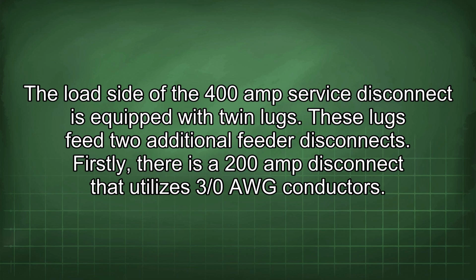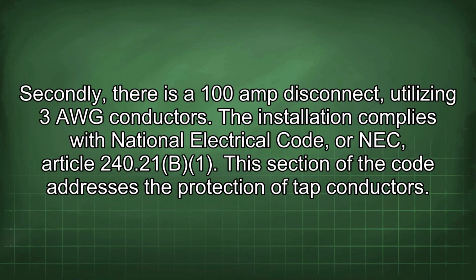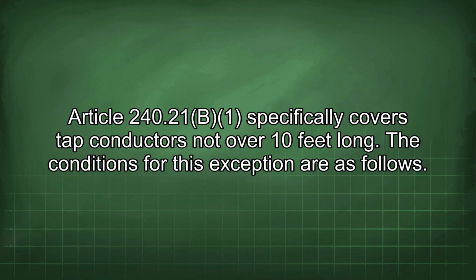Firstly, there is a 200 amp disconnect that utilizes 3/0 AWG conductors. Secondly, there is a 100 amp disconnect utilizing 3 AWG conductors. The installation complies with National Electrical Code, or NEC, Article 240.21(B)(1). This section of the code addresses the protection of tap conductors. Article 240.21(B)(1) specifically covers tap conductors not over 10 feet long.